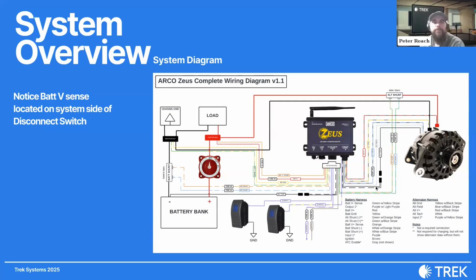Over on the left side of the diagram, I'll point out we have the battery shunt there, and this one does have those battery shunt plus and battery shunt minus cables going to the shunt so we can get that data into the Zeus. Like I mentioned previously, if you do have a Cerbo GX in the system, that will communicate to the Zeus. One other thing I want to point out is the battery voltage sense is on the system side of that battery disconnect switch - we'll talk more about that in a bit.